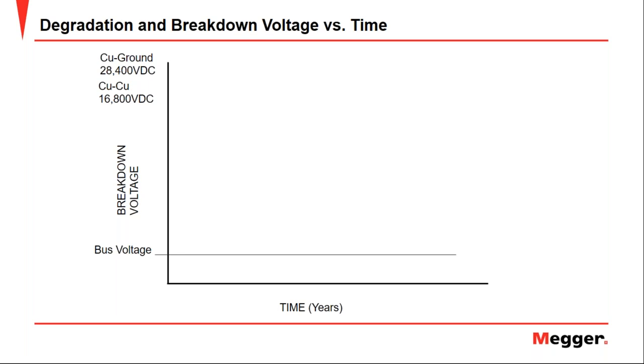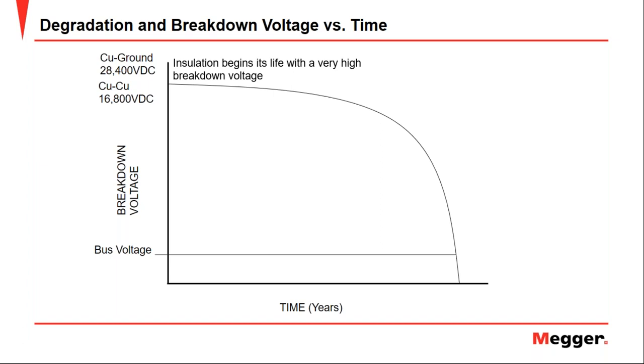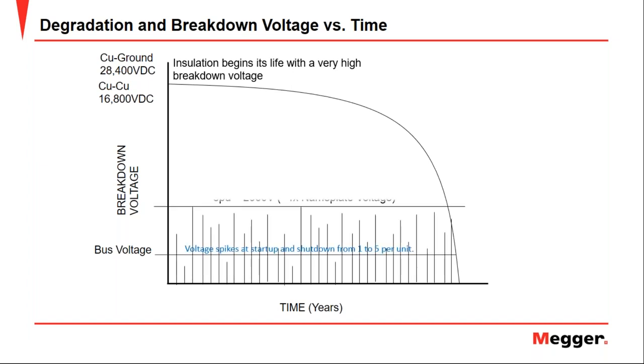Also, it's evident that when the motor is new, its insulation system is optimal. It is the best possible, and therefore its breakdown voltage is high. But as time goes by, due to the effects of temperature, contamination, humidity, and mechanical conditions such as imbalance and misalignment, the insulation system degrades until it intersects with the bus voltage. At this point, when the two curves intersect, the motor failure occurs.